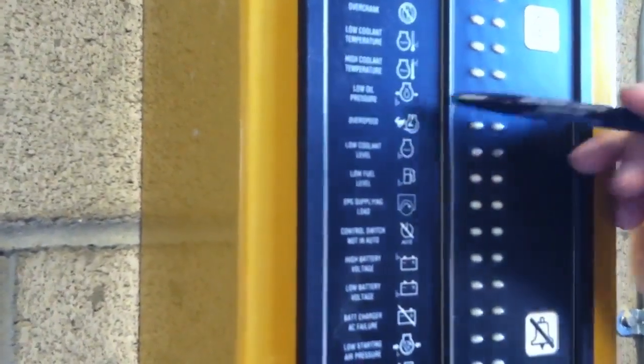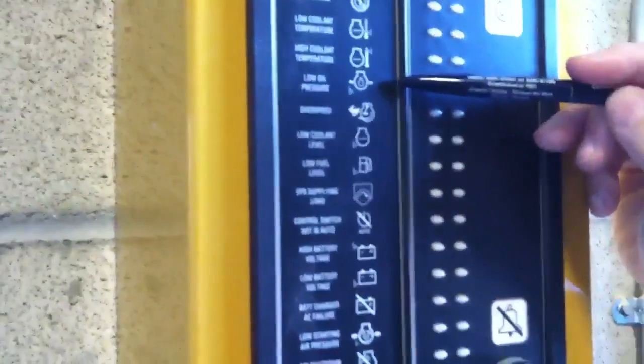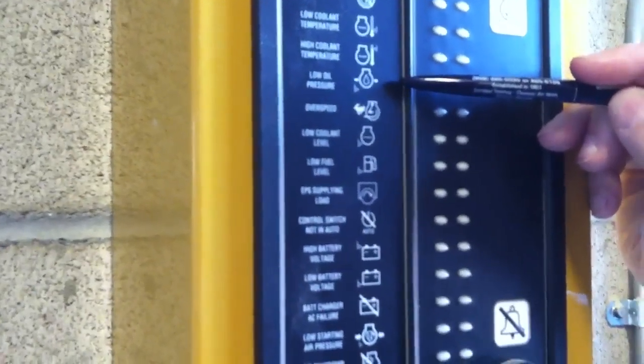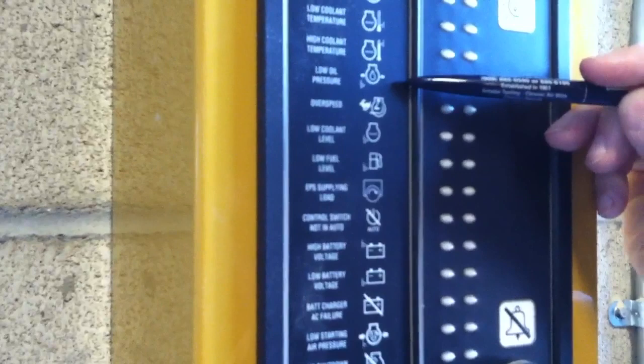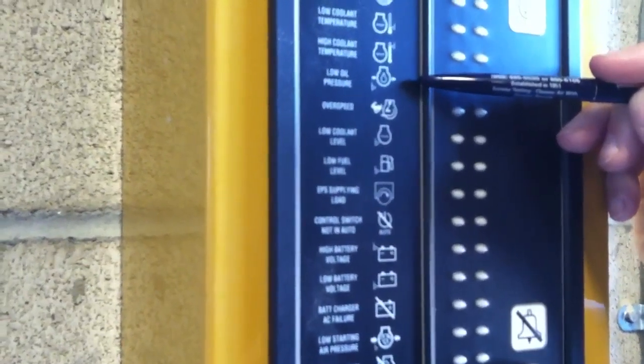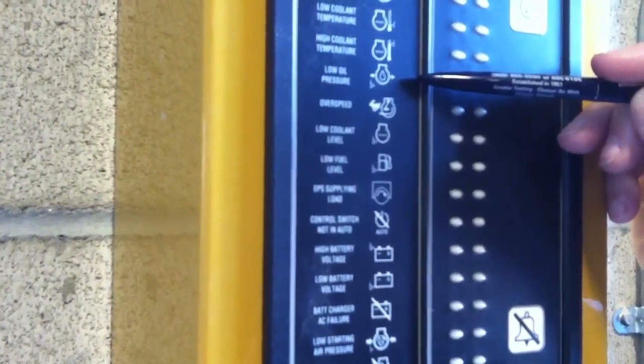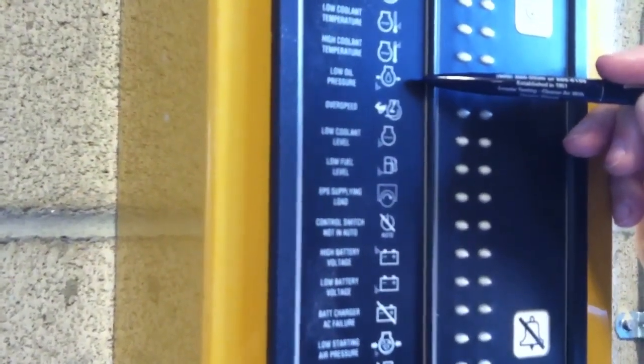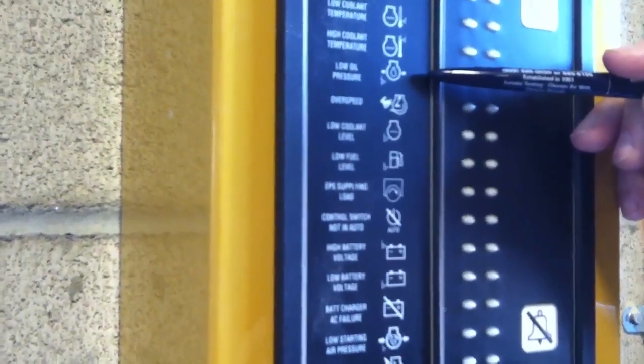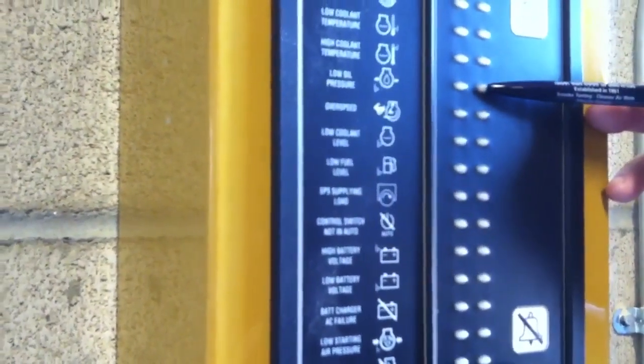Low oil pressure is if we talked about oil pressure between about 50 and 80 psi. If we get down to about 25 psi which would mean we're either out of oil or we had an oil pump failure we're going to get a low oil pressure.